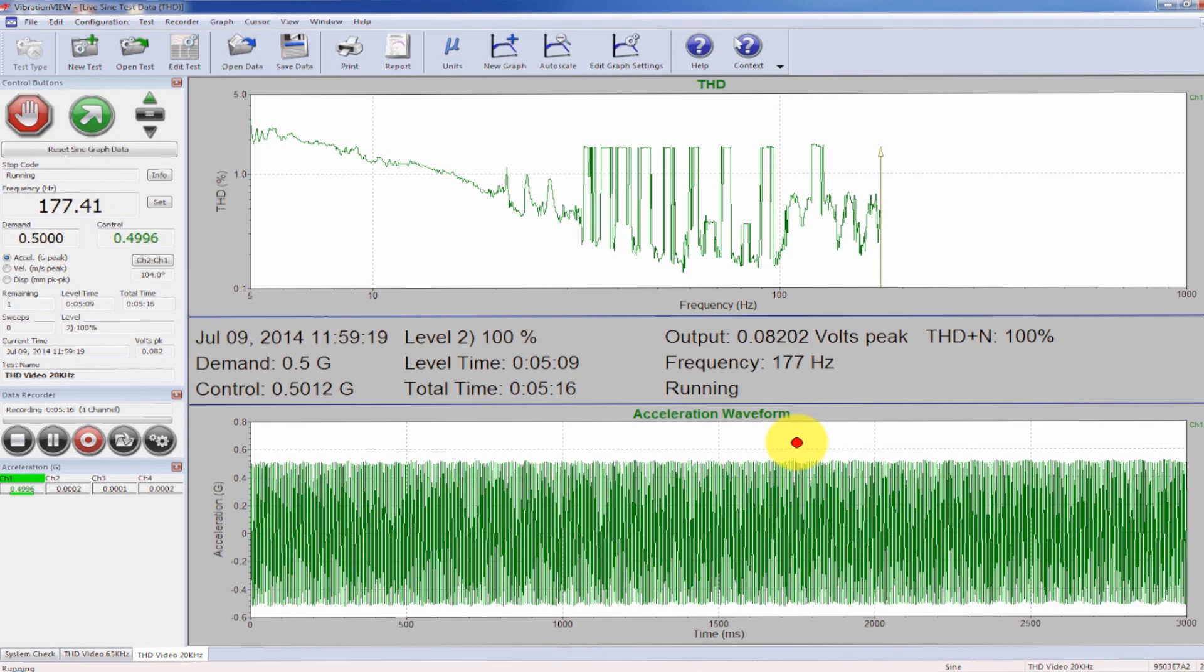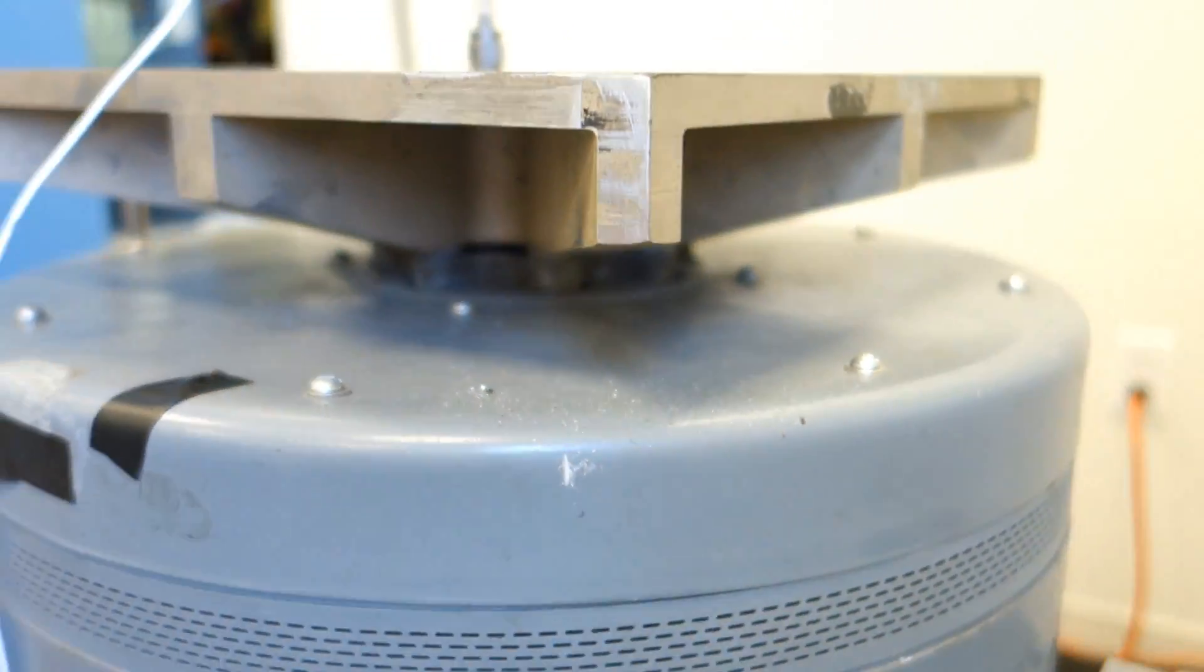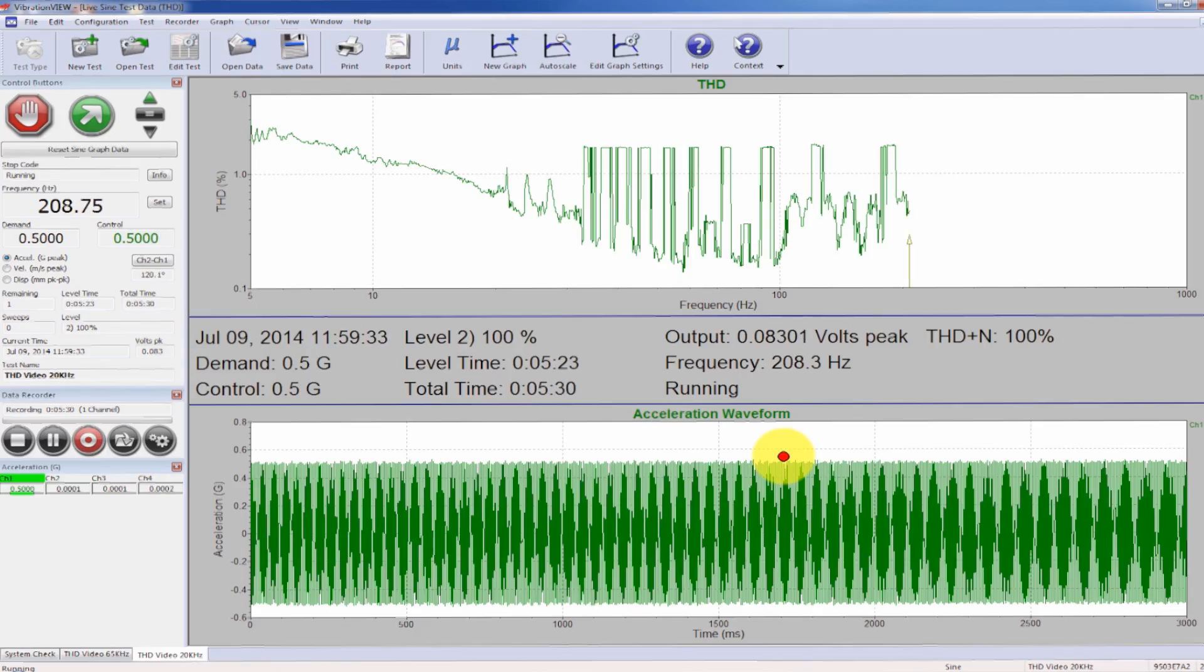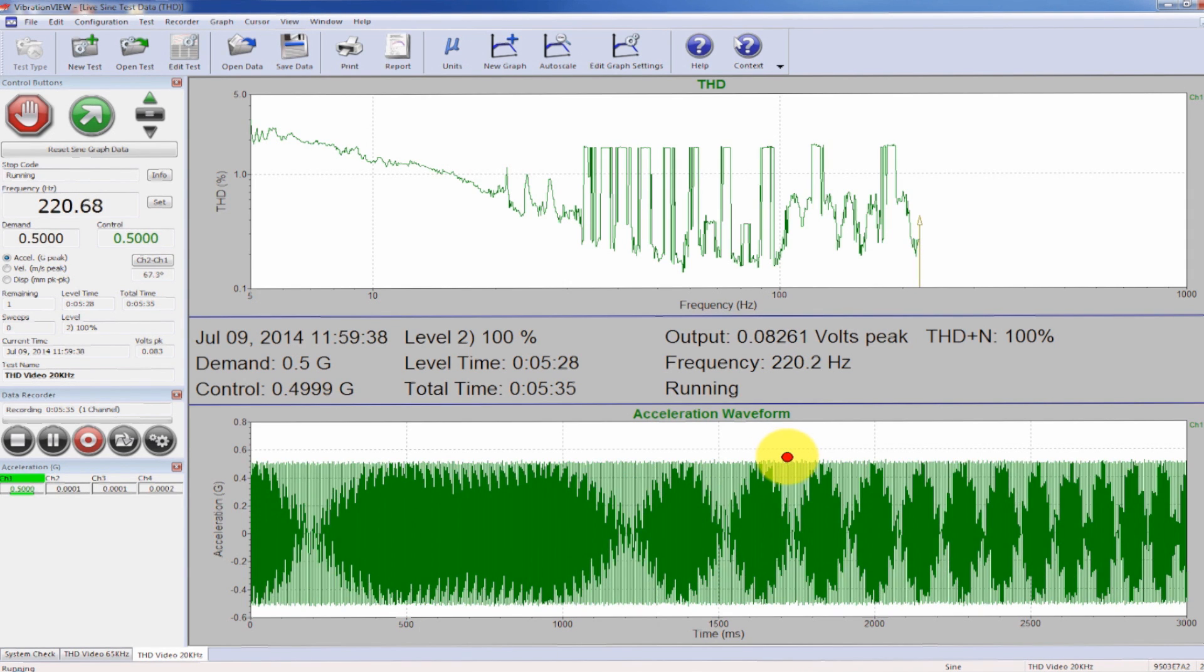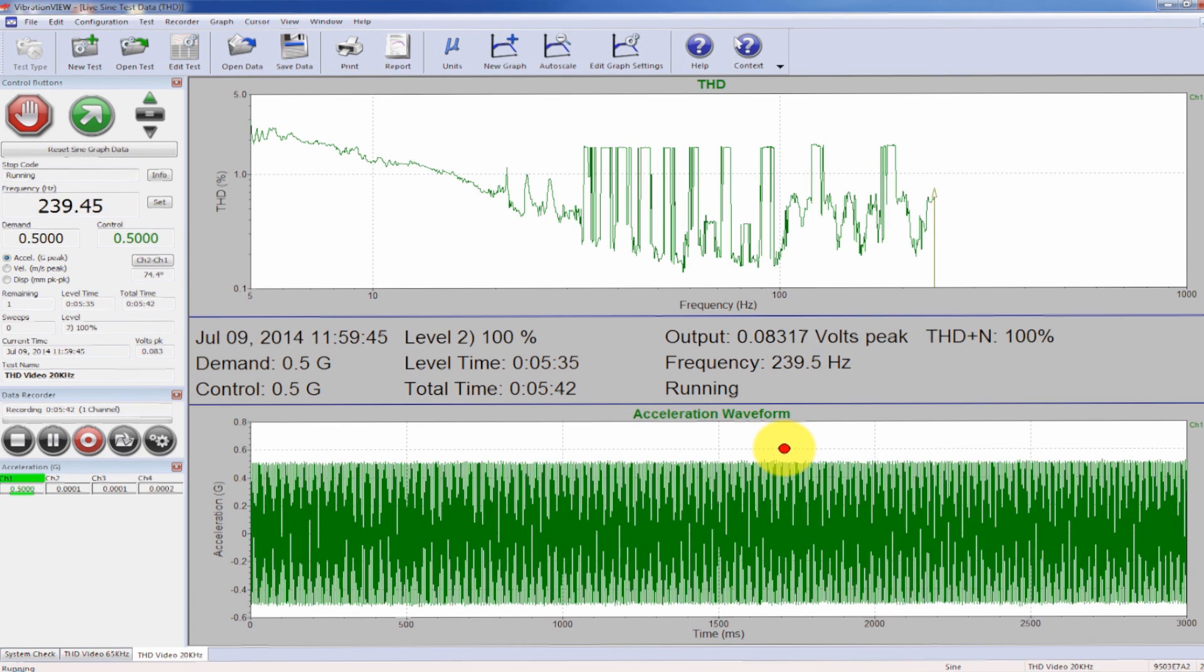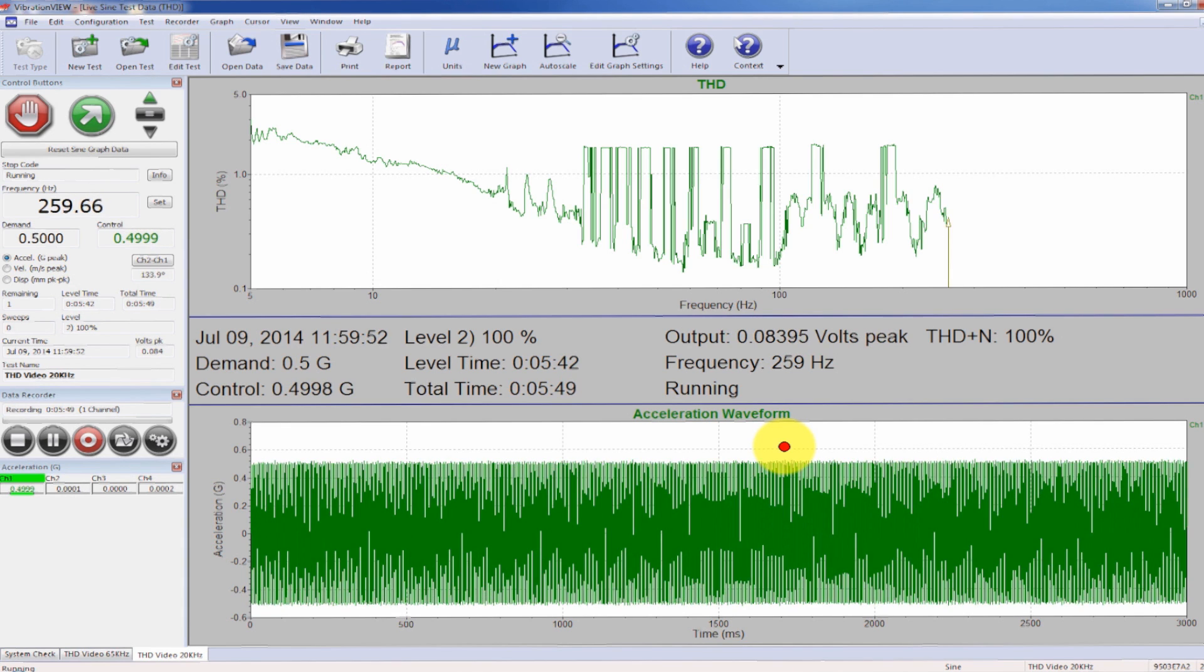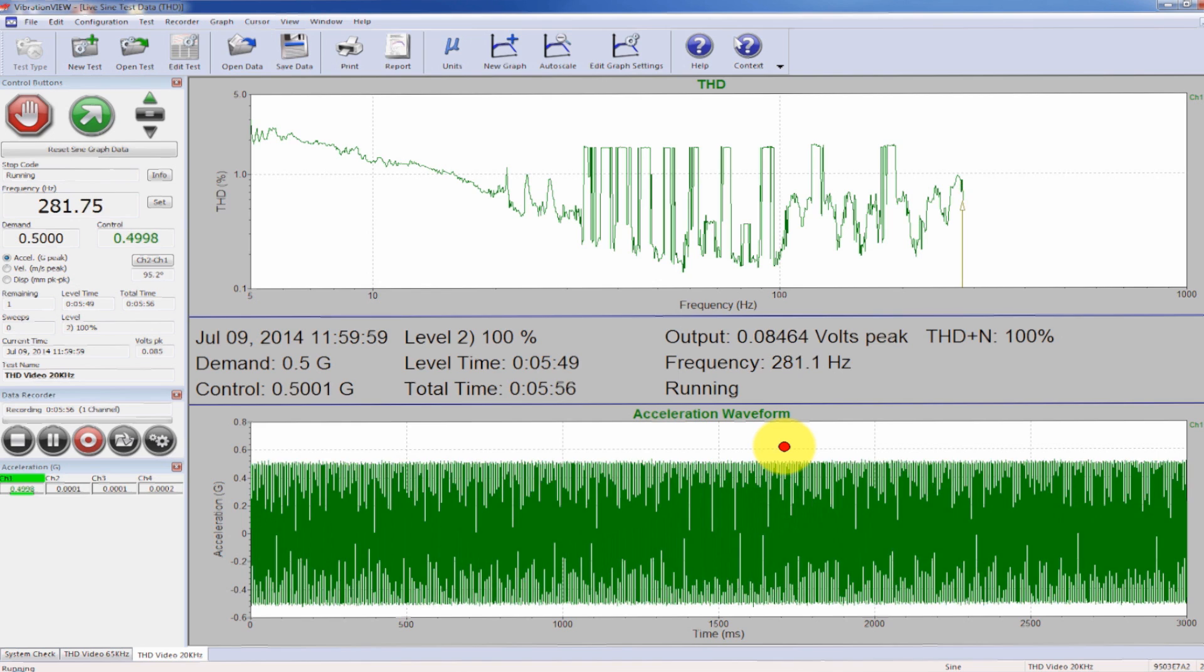I'm running this with a head expander, a bare table though, so I don't have any type of product or fixturing on this. If I were to remove the head expander and run this directly on the armature, I may get even better results. You could do some comparisons by adding your fixturing and doing another sweep and determining how well that fixture is designed and how well it's transmitting those frequencies from the armature through the head expander and into the fixture and finally the product itself.